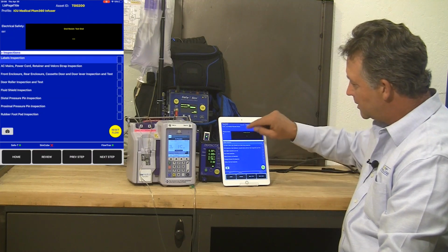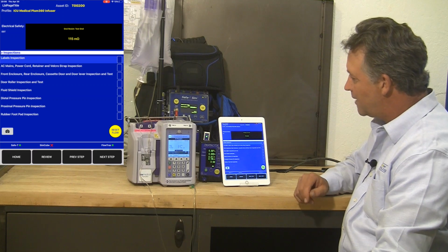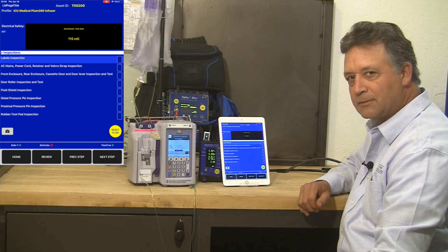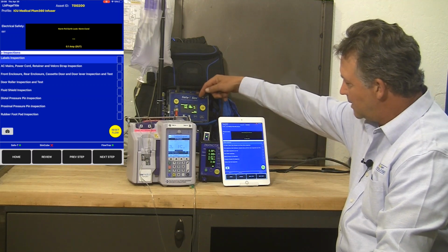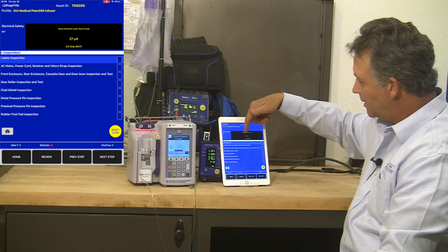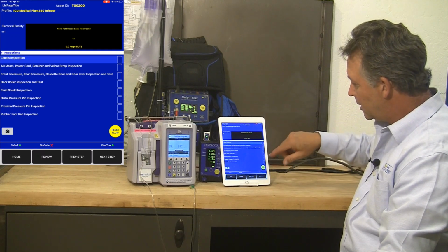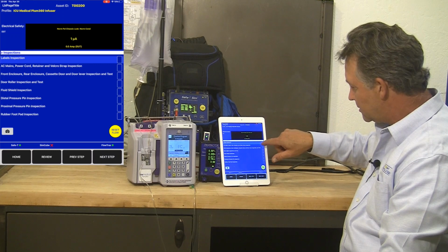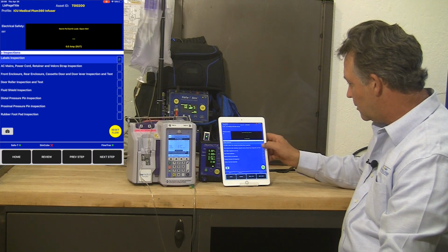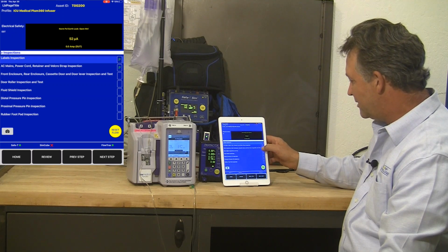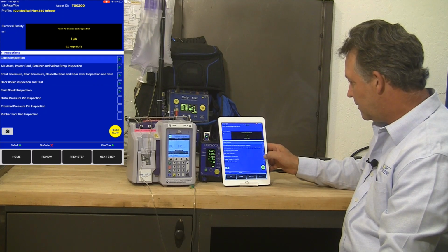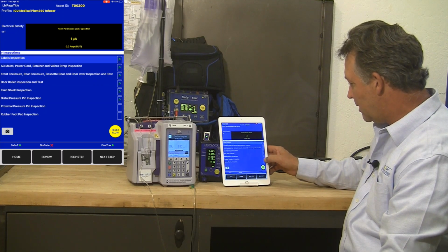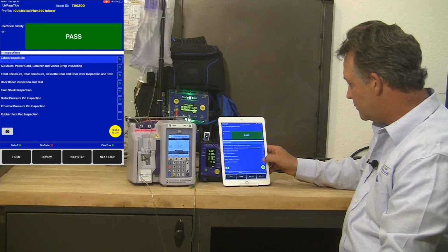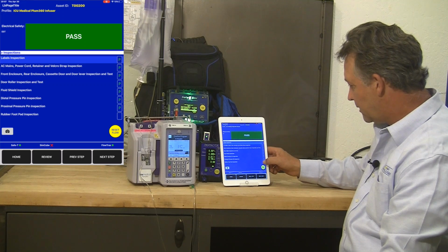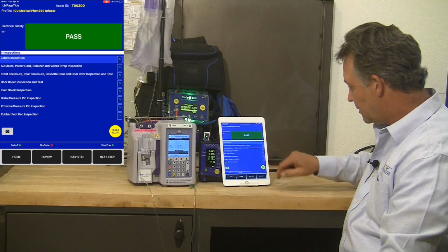As soon as I hit start, it's going to start a predefined electrical safety test per the manufacturer while I walk through visual inspections and select pass-fail. So I can see the safety analyzer is running tests that are predefined, and I can see those results as they're coming through on my iPad. So I'm going to go ahead and do the label inspections, the AC mains and power cords. I'm not actually going to do any tests or visuals in this case because the video would take too long. We'll just do pass-fail for the various testing and inspection that's required other than volume and occlusion, which we will do at the end. So I'm hitting pass-fail on each of those right there on the touch screen.